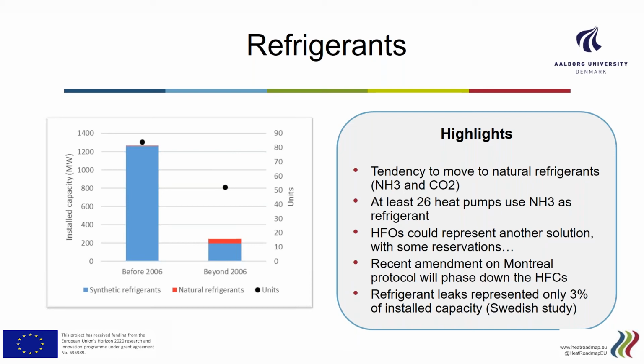However, options and variants exist to replace this refrigerant and have different types of heat pumps, and that would be heat pumps using ammonia, carbon dioxide, isobutane, or hydrofluoroolefins. I will say a few words about these refrigerants, so you get a better overview of their advantages and disadvantages. So ammonia is a refrigerant generally used in medium and large-scale applications.